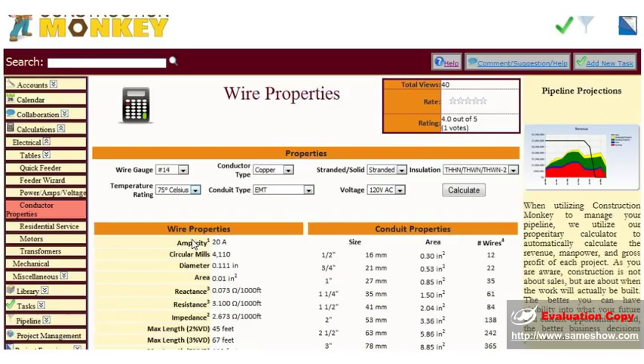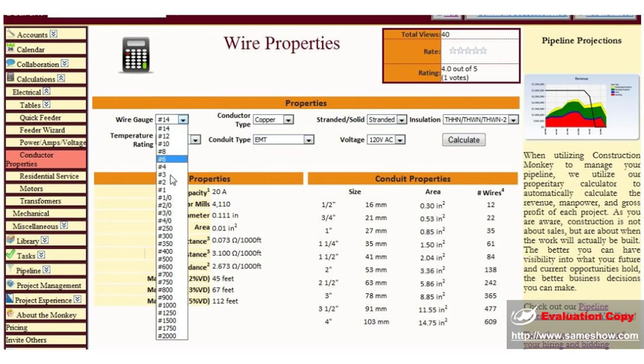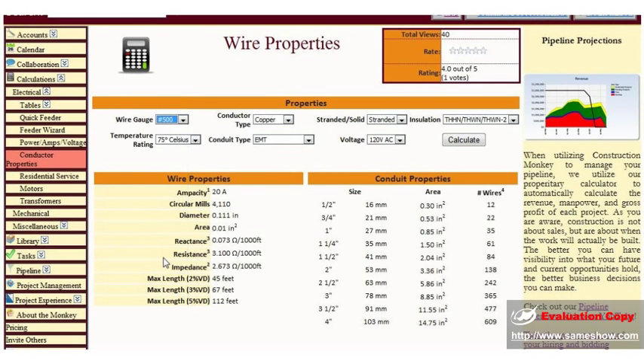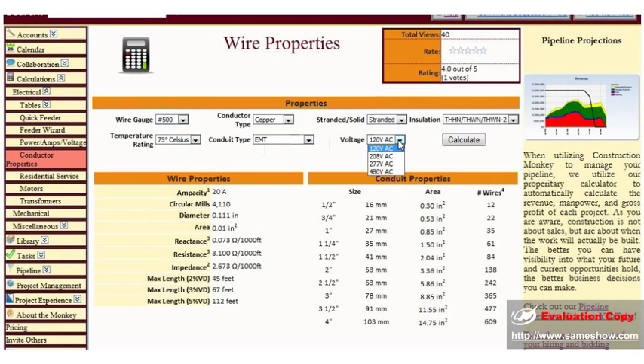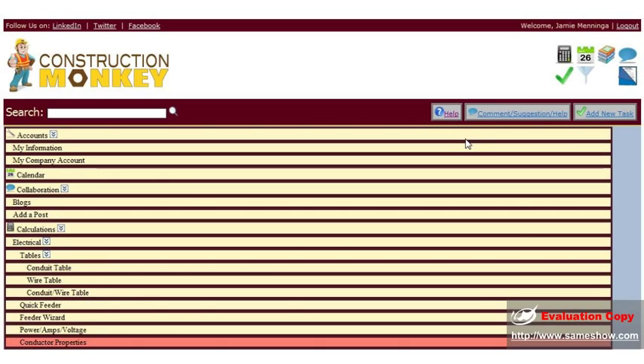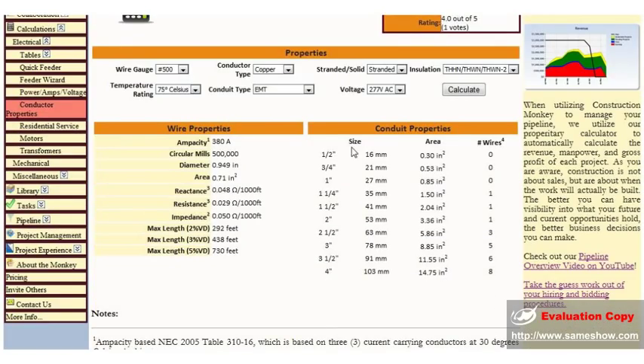We also have a conductor's property calculation, where you can find all the wire properties of a certain type of wire. Say we want to know what 500, copper, stranded, THHN, 75C, and EMT. Let's say it's 277 volt. Calculate that.